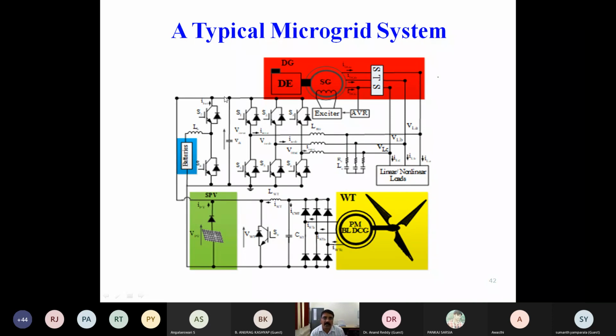Here the system is controlled such that maximum power point tracking is done with this converter for the solar photovoltaic, and maximum power point tracking of the wind turbine is done with this DC converter. At this DC link, since this is a permanent magnet brushless DC generator with the wind turbine, it is to be rectified. Then the DC is connected with this DC link, and this combined DC link is inverted to match the linear or non-linear load or AC requirement. A diesel generator is connected for backup if any of these sources are not available. That is important - it is a standalone kind of connection.